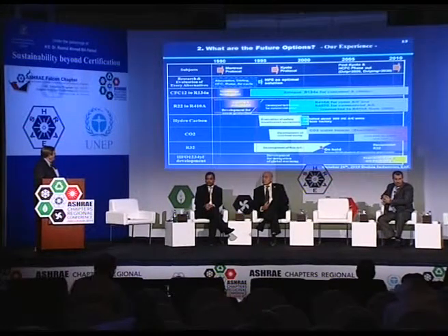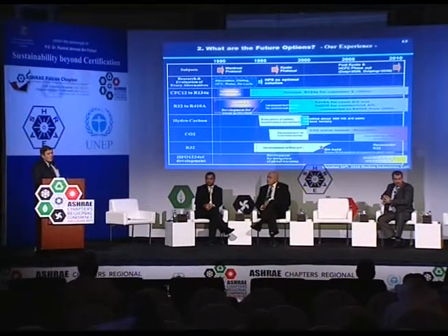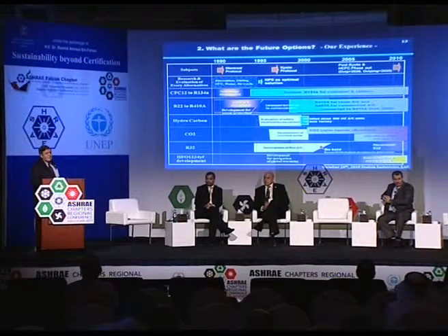Look at what happened back in the 90s: we took all the CFC designs and converted them to 134A—not a major issue. In the R22 designs, we initially converted them to R407, a drop-in substitute, until R410 designs could come out that could handle the higher pressures. That's basically all done now, and it went very smoothly.